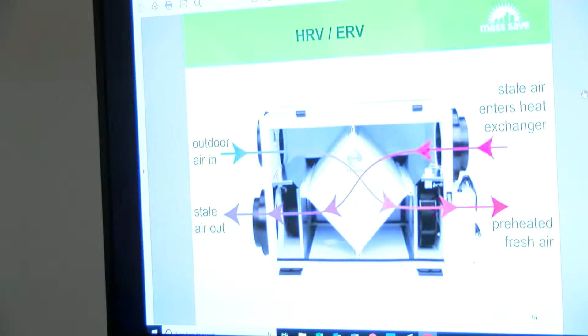So all the calculations are done, how much we're ventilating and how much we're taking in. And again, that intake air or makeup air is being brought through that manifold, and you're exchanging or tempering the air before we put it into the furnace, creating less BTUs to heat or cool in the heating or cooling months. Exactly. Yep. The fan draw is one part of it. So you figure out how much that fan costs, as Peter was saying. But the other cost is conditioned air that you're now putting outside. So if you don't have an ERV or an HRV and you have a fan only, you also pay a financial penalty on that air that you heated or cooled that you're now pumping outside. So they are more to buy up front, certainly, and install, but there's certainly a payback over a certain amount of time where you're saving on your utility bills. Yes, as well. Excellent. And of course, the filtering is nice.